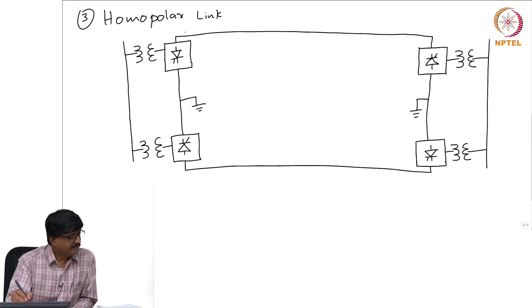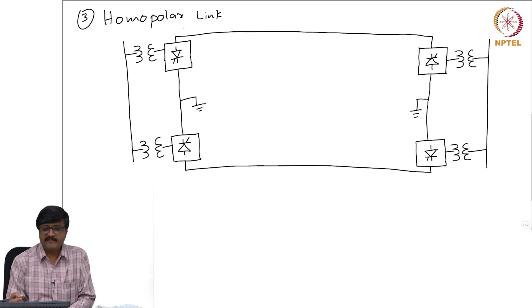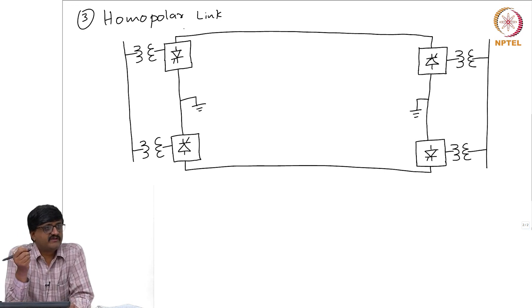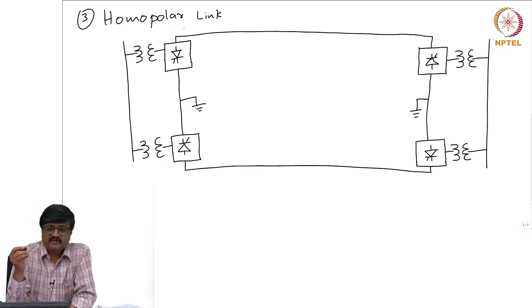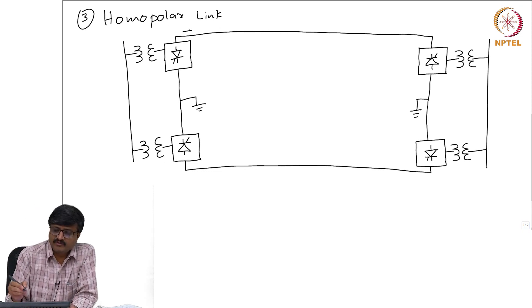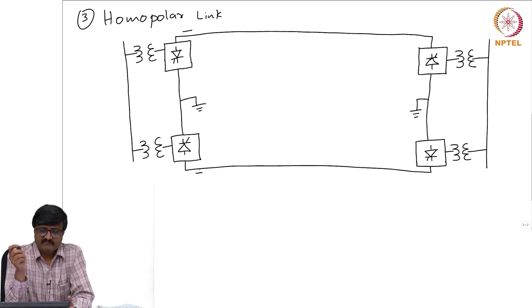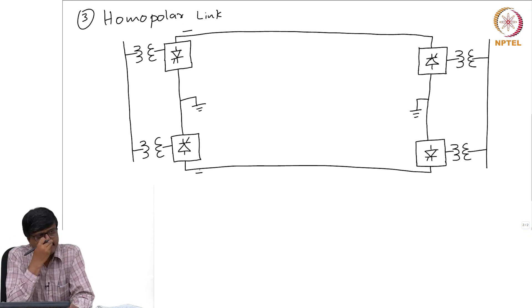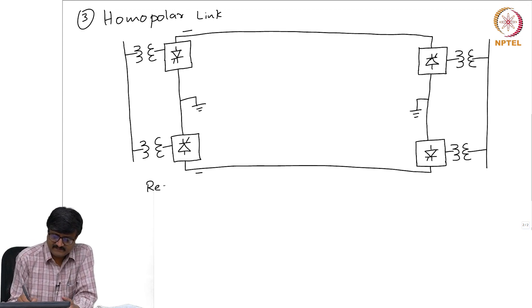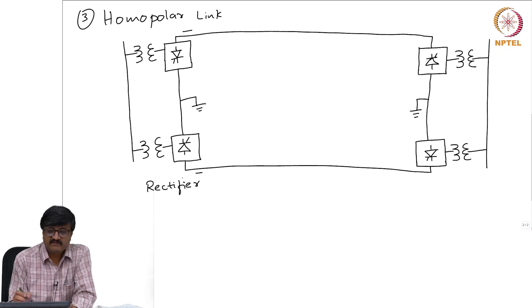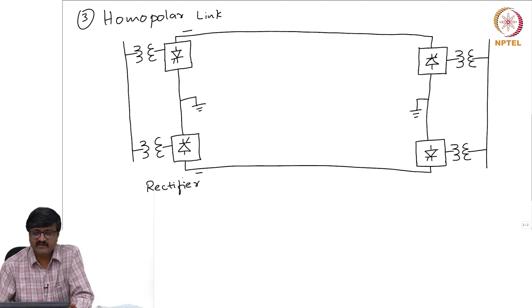In the case of homopolar, both conductors are at the same potential with respect to ground, and we saw that having negative potential will result in less corona compared with positive potential. So both the conductors are at the negative potential. Again, the left side is rectifier — it is the rectifier. Please note this is different from bipolar; notice the difference between the bipolar and the homopolar links. And this side is the inverter.